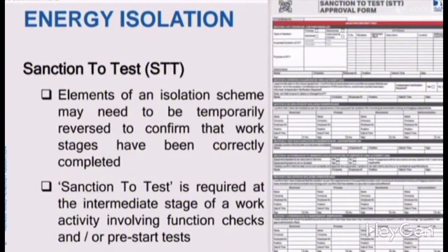Sanction To Test. STT is one of the most important certificates. Elements of an isolation scheme need to be temporarily reversed to confirm that work stages have been correctly completed. In any condition where during work activity we need to temporarily bypass isolation, remove isolation, or restore the energy source, we must restore the particular type of energy with the equipment and check whether the work stage has been properly completed or not.